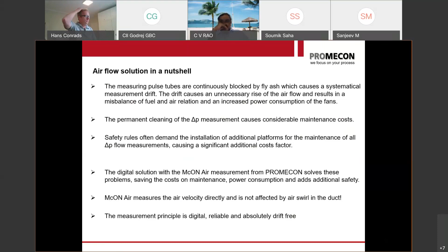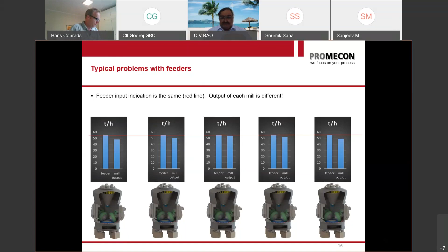Don't believe that this is correct. Your feeders are drifting as well. Every operator in a power station knows he has to correct the feeder lines from time to time. You put something into the mill, but you always get out less, because moisture evaporates. More importantly, the coal output of your mill differs from mill to mill because your feeder input is not accurate. You do not have the same output on every mill. That's a fact, as you can see from the enthalpy calculation and the mass energy balance.